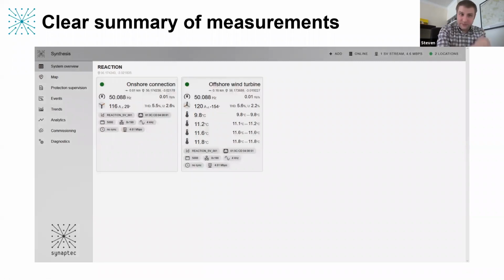This next screen gives you a summary of the main electrical and mechanical measurements being observed by the system across all locations. In this case, there are just 2 locations, but it would scale to many other locations in different installations. Here you get a summary of all of the measurements for each distinct location. For voltage and current measurements, it automatically calculates synchrophasors and system frequency and other interesting metrics such as THD and imbalance. For temperature sensors, we get the instantaneous value and a range of values over a period of time.